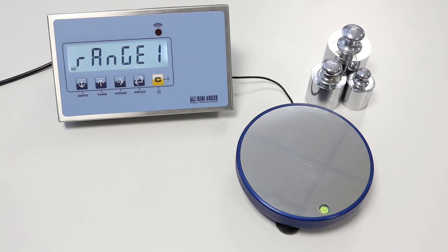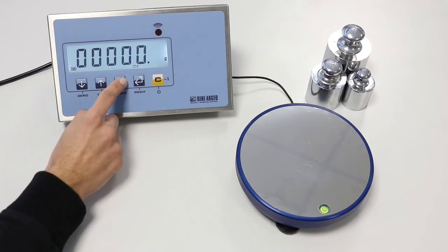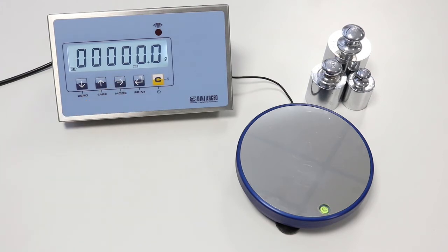Range 1 is the maximum capacity for a single range scale, or for multi-range scales as in our example, it is the first range. C key erases the values. Mode key allows to scroll the number from left to right. We need to set 1500 grams.